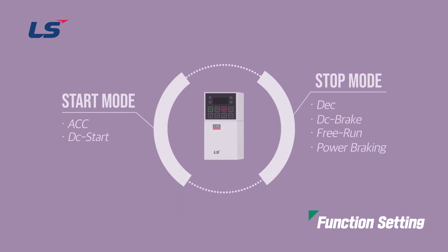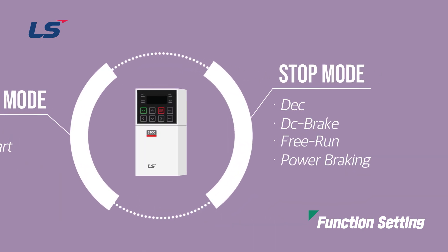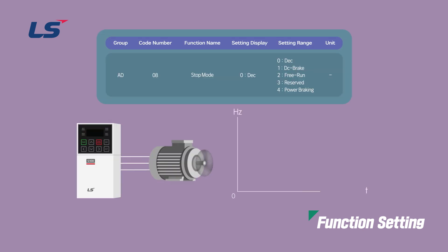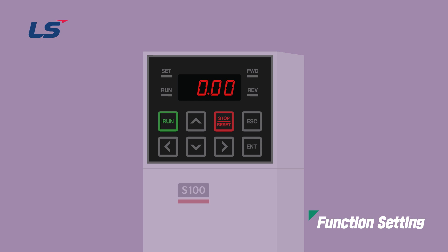Let's see how to set the stop method. The DEC stop method is a general deceleration stop method. If no other function is selected, the deceleration time will be affected by the deceleration time to slow down to 0 Hz and then stop. In the AD8 stop mode, press the enter key to set the stop method. Use the arrow keys to move to 0 DEC and press enter to complete the setting.